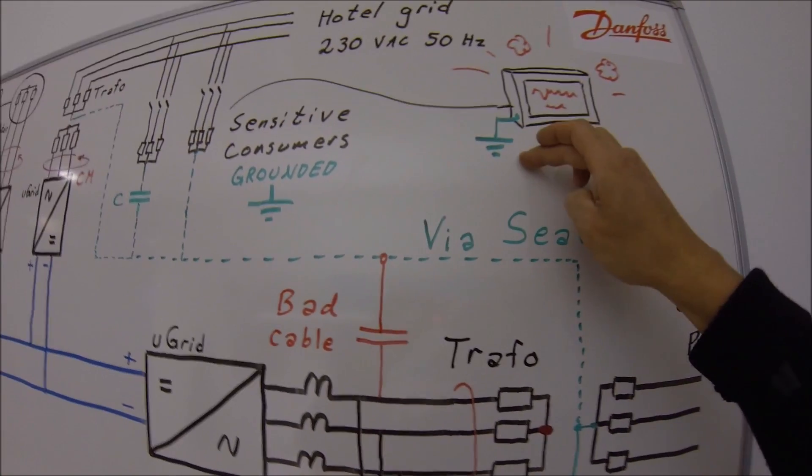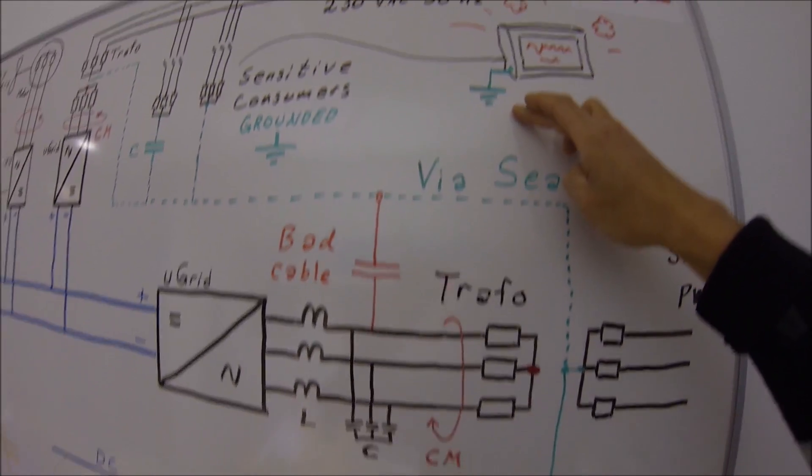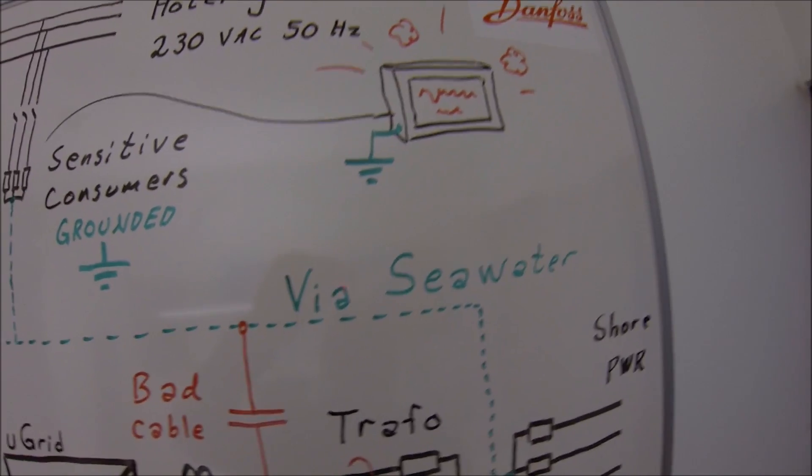You have high stray capacitance between the phases and the protective earth. So you have contaminated your protective earth. Then, even though you got clean power from this side of the transformer, you have the EMC and common mode transferred via the protective earth.